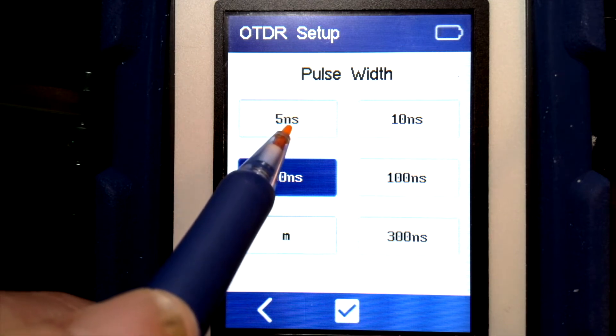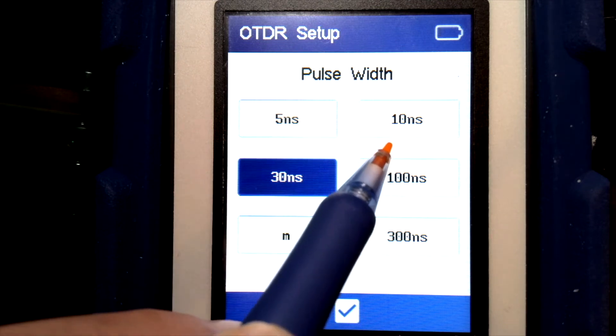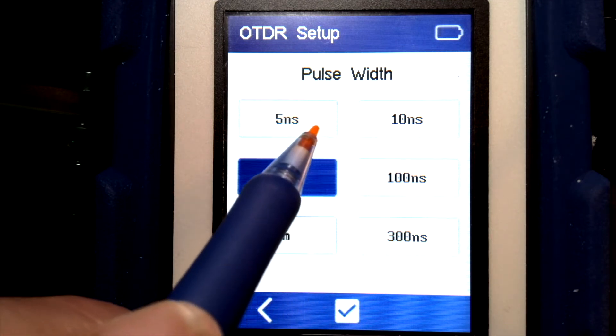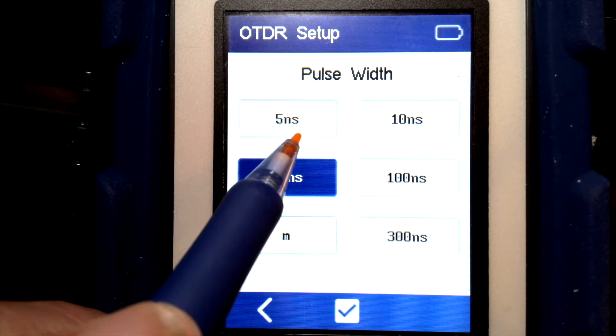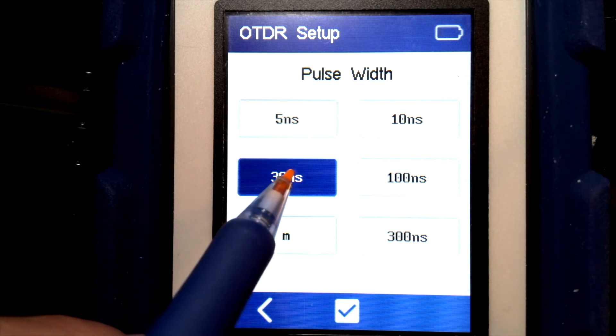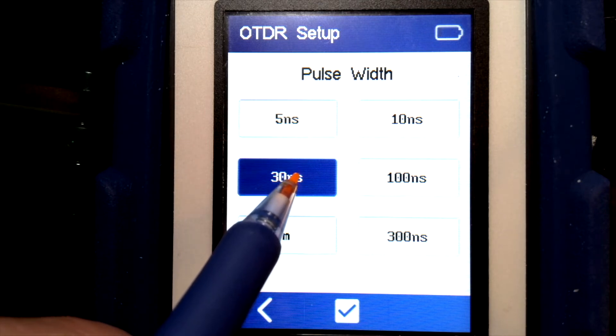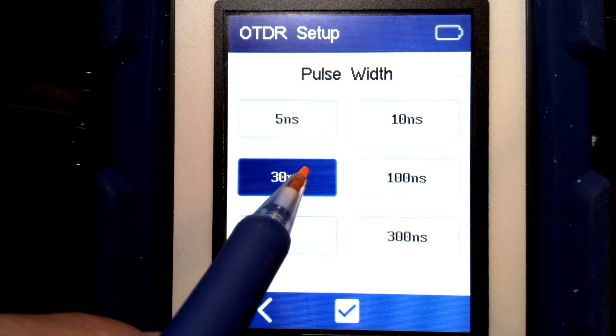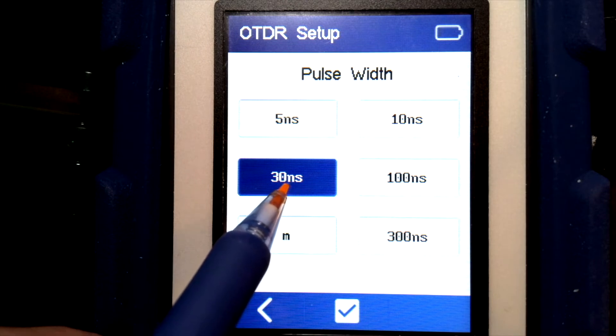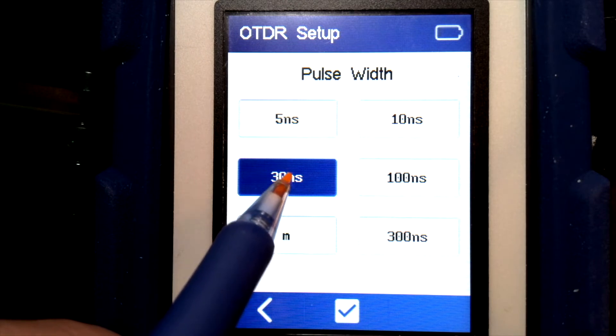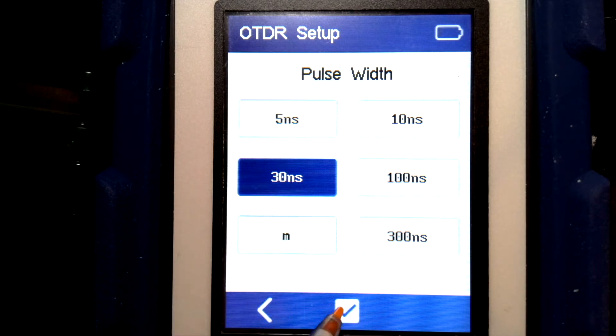We can go with 5 nanoseconds or 10 nanoseconds to get a shorter pulse and a shorter dead zone. But with multimode fiber of the type we're testing, 30 nanoseconds will give us enough power to measure out to the end of the 600 meters.